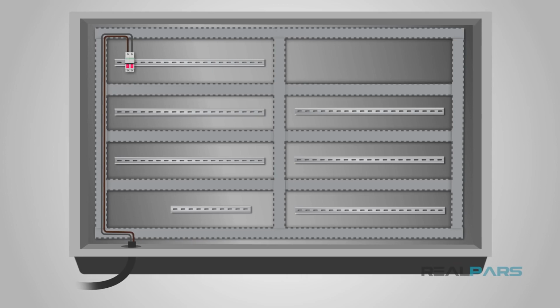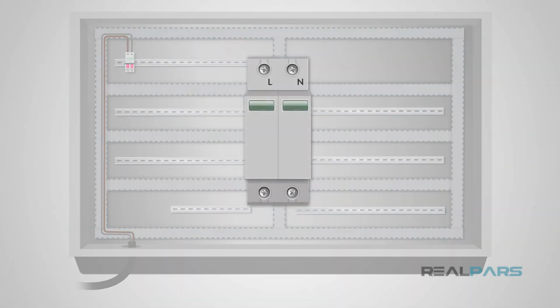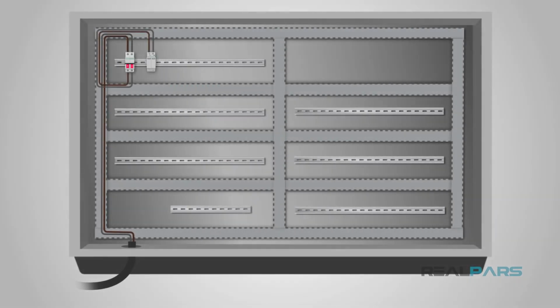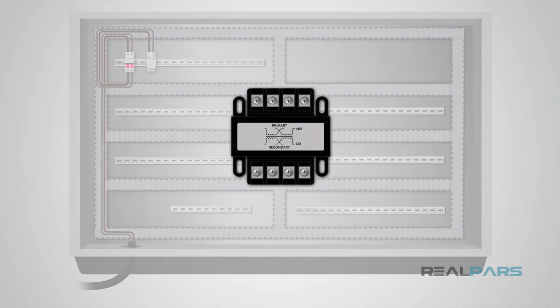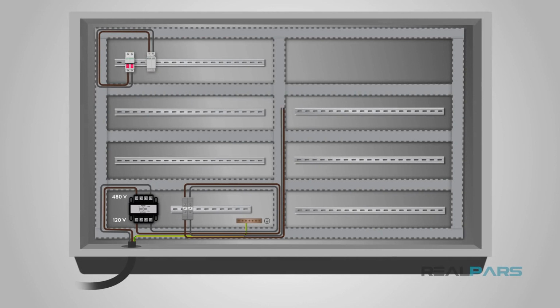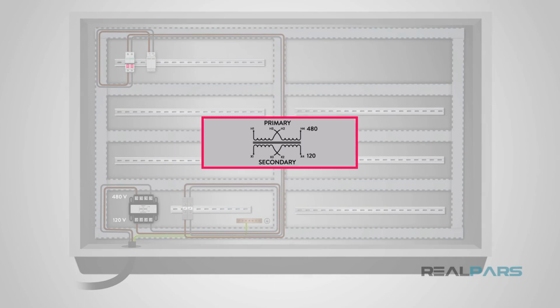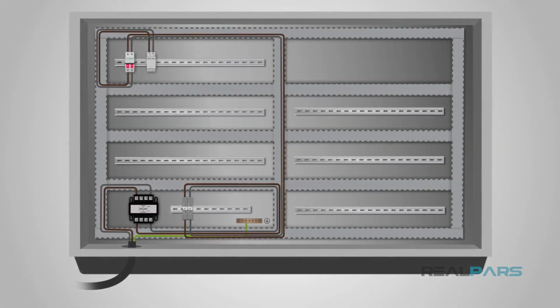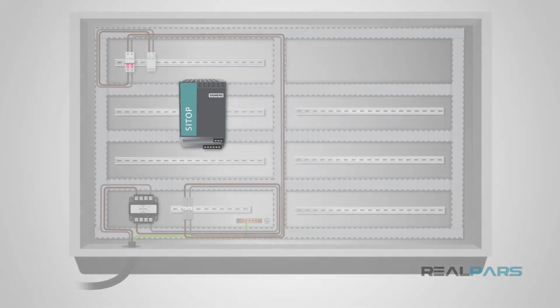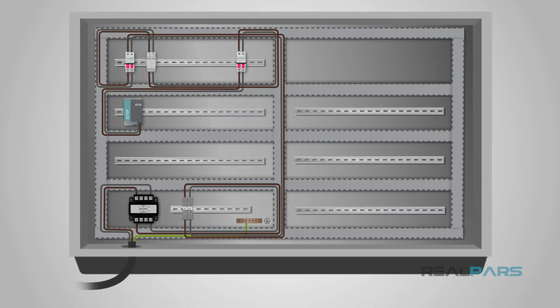After the power comes into the panel from the main circuit breaker, the power will be run into a surge arrestor. A surge arrestor is a device that protects all of the electrical equipment inside the control panel from electrical surges or overvoltage. An electrical surge can come from a lightning strike or utility power surge. The power can be connected into a transformer that steps the power down in order to power smaller devices. If the incoming power is above 120 volts, a transformer is generally used. If the power is 120 volts, a power supply can be used to step the power down to 24 volts.